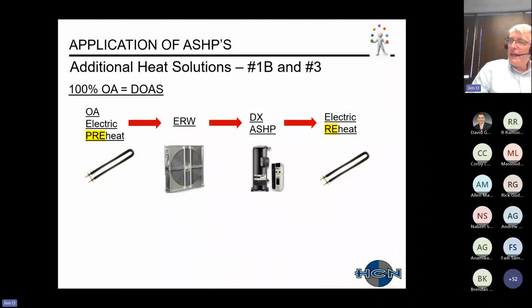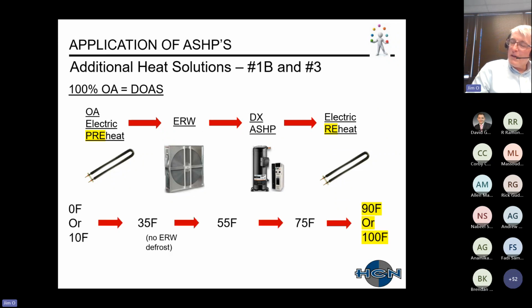The last couple of slides for the application: let's look at additional heating solutions. This is 1B, where you're adding the outside air electric preheat as well as the energy recovery wheel. I switched this one to 100% outside air. So this is the path of our outside air as it gets heated. These are some appropriate temperatures. Start at 0 or 10. Size your electric heater to 35.